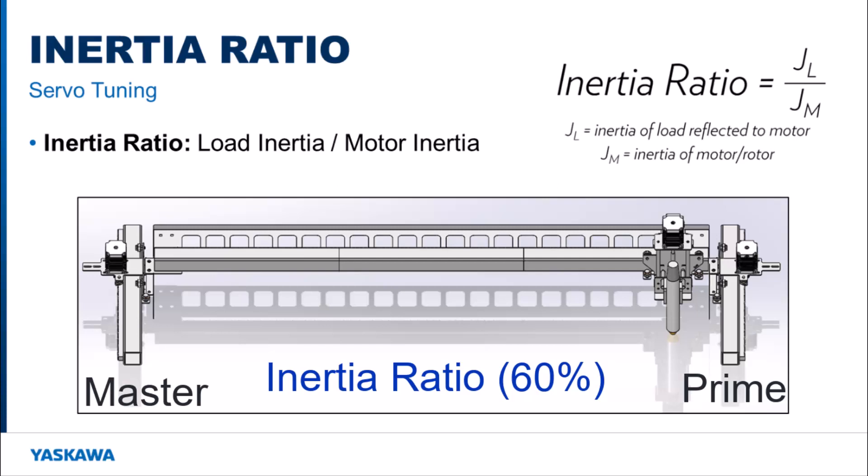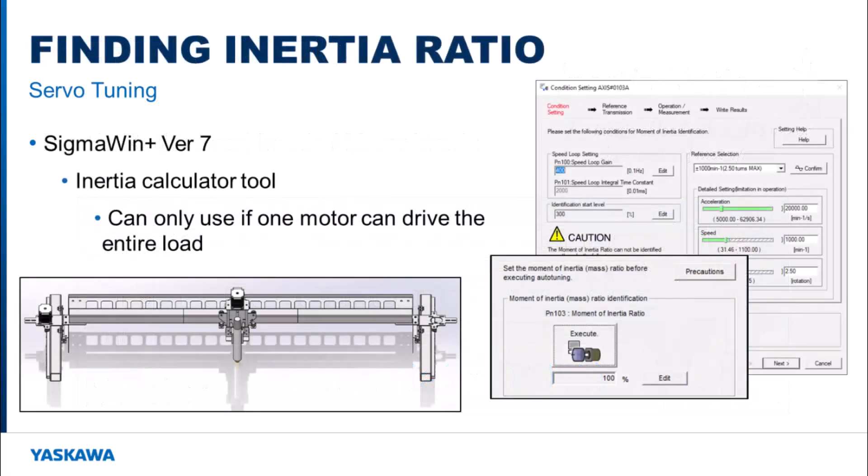In a system like this, how would one go about finding the overall inertia ratio? If one motor is able to move the load, the inertia calculator tool can be used within SigmaWin+. The prime axis motor would have to be disconnected and then the tool can be used to estimate the total inertia. The load should be centered as if both motors would see the same load, even though the prime axis is disconnected. Since this is finding the total inertia ratio of the system, a percentage above 50% should be applied to each motor. If the prime axis motor cannot be disconnected or if the structure is not rigid, then the inertia calculator tool cannot be used.